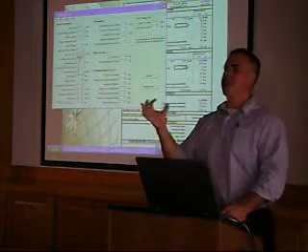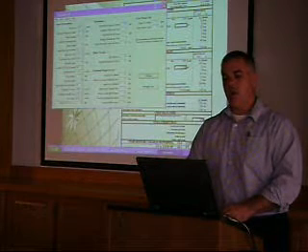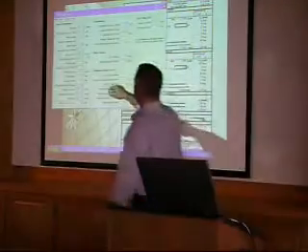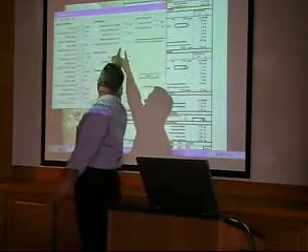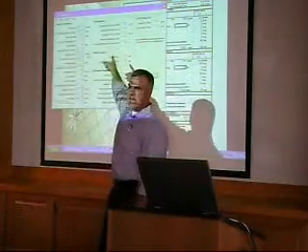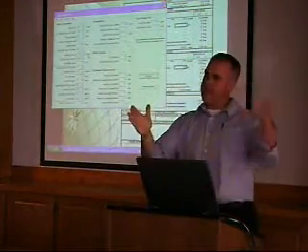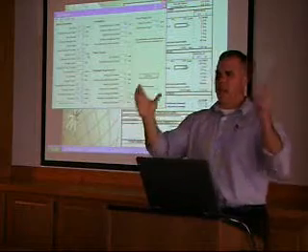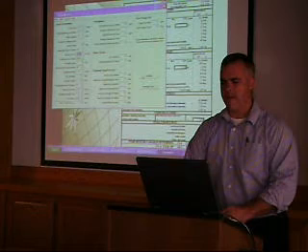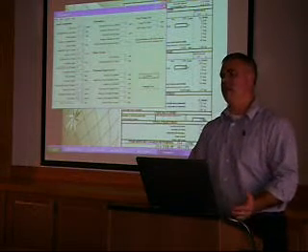Now I want to show you what happens when I change the lateral diameter. We just talked about choosing the lateral diameter, and I showed you that chart. Let me show you in real life what happens here. Okay, maybe we could get away with, in this scenario, a 1 1/4 inch lateral diameter. You see where we're approaching 10, and that is again from beginning to end. I want no more than 10% so that I get equal flow. If I throw in there 1.5 inches, see how it goes down?